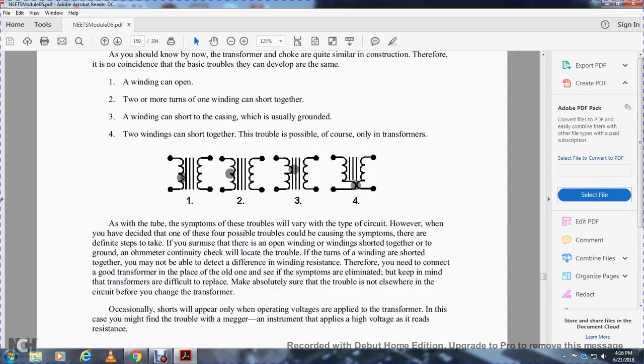As with the tube system, the trouble is traced to the circuit; however, you decide which one of the four possible troubles is caused in the circuit symptoms. There are different steps to take. There is open winding, winding shorted together, and short to the ground. Use a meter to check and localize. To locate trouble of turns in windings that are shorted, you may not detect the difference in winding resistance. Therefore, you need to connect a good transformer in place of the old one. See, the symptoms are all eliminated.